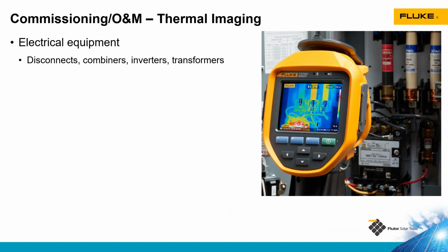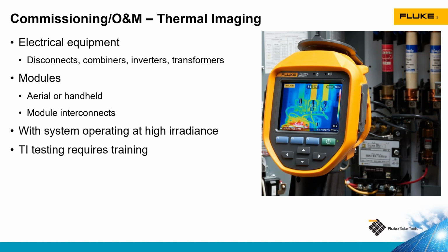Now in commissioning and in operations and maintenance, we can also do thermal imaging. Thermal imaging can be used on all kinds of equipment. We can use it on our electrical equipment, things like disconnects, combiner boxes, inverters, transformers, any type of electrical equipment that's got connections or electronics in it. We also see thermography of modules done very extensively in solar, especially aerial thermography, where they use a drone to fly over the array with a thermal camera. They take images, they analyze those images with a piece of software, and then they can identify areas that need further attention. When you're doing thermal imaging, you need to make sure that the system is under high load.